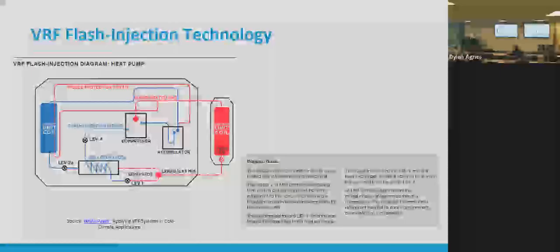But yeah, the compressor. The reason inverter-driven heat pumps are so important in cold climates compared to a constant speed compressor is they can vary. They have lots more levers to pull. They can vary their suction pressure, which is what's required to suck heat out of colder and colder air. So they keep going lower and lower. They just have to run faster and faster to drive down suction pressure and still maintain a reasonable discharge pressure to reject heat through the condenser.